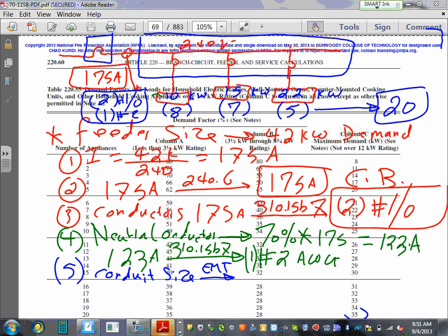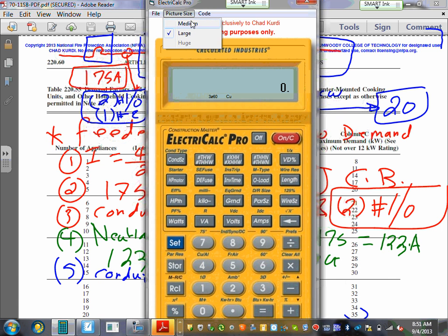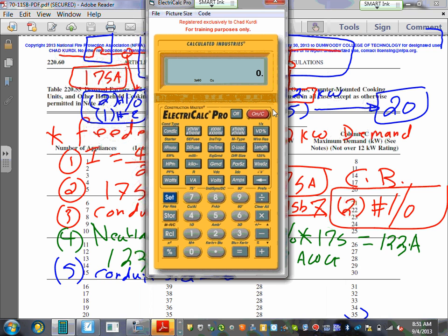So let's go directly into it. Okay, here you go. Remind me what the sizes are. Here's what we have. We have 1 aught wire size. How many of them do I have? I have 2. What insulation? We're using THHN. THHN, enter. Then I have the number 2 wire size. How many of them do I have? 1. What insulation? THHN. Click again.